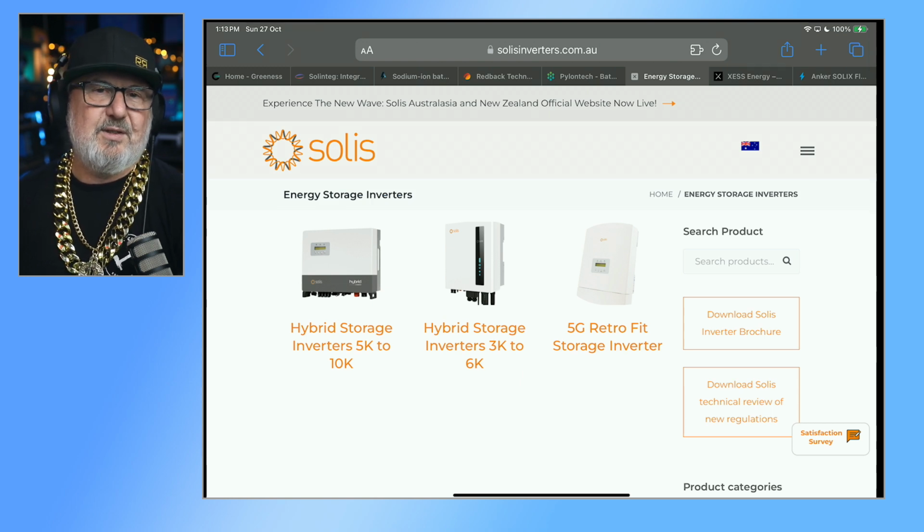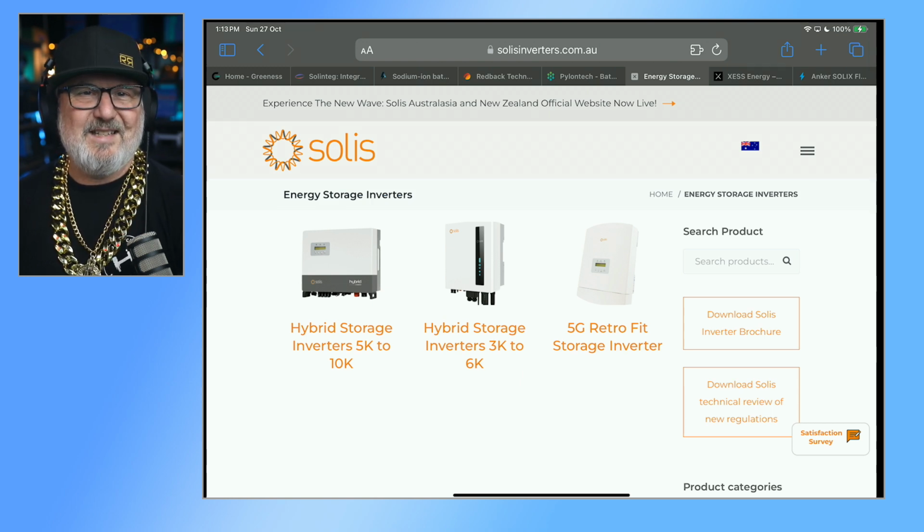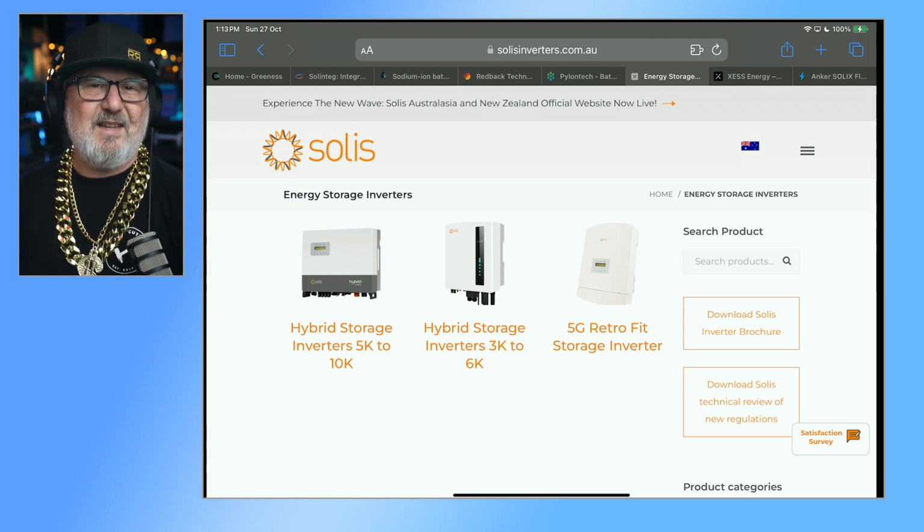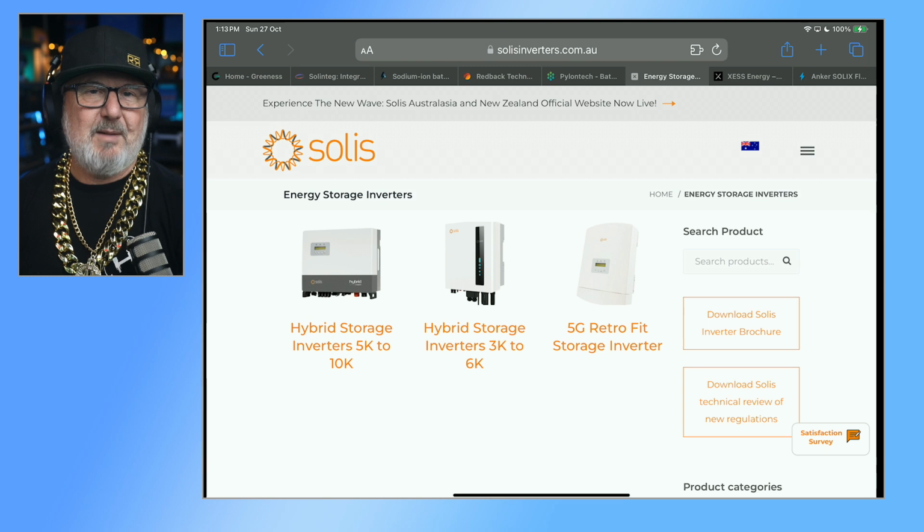And of course, certainly for those of us who live in the southern states, every day isn't a sunny day. And on a less than perfect day, your 16 kilowatts of solar might be only putting out 4 or 5. So it just means that you're always getting a high solar fraction from your inverter. So that's another thing. Oversizing is really big.